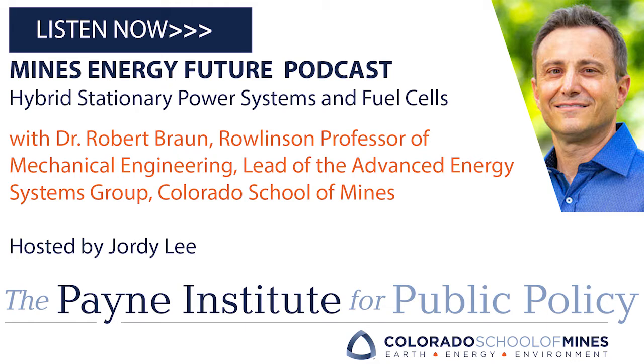And so that's one of the reasons it's so exciting for us. Usually you see such hybrid system technology only reaching 50 to 60% efficiency. An example would be the very large scale natural gas combined cycle, which takes your old school Rankine cycle steam power plants and integrates that with gas turbines. And together they have two shaft powers that make electricity in the end and achieve the high 50s, perhaps 60% efficiency. But they are very large, 400 megawatts or larger.